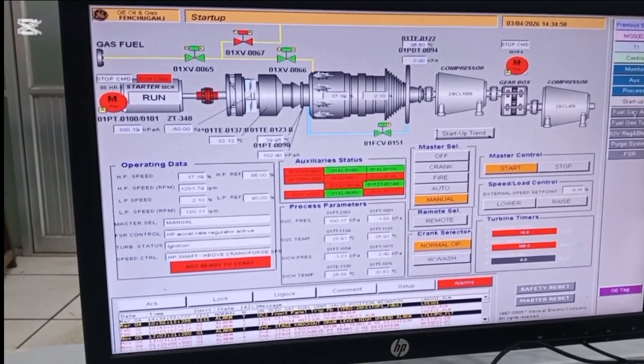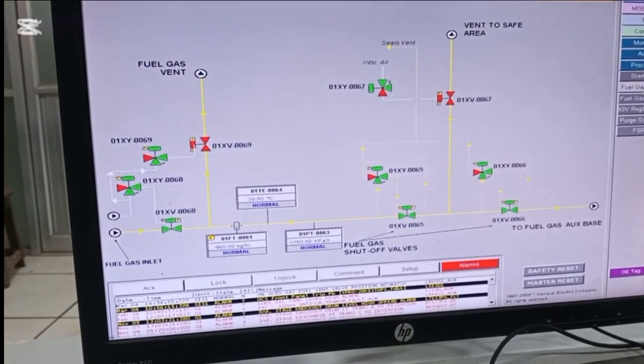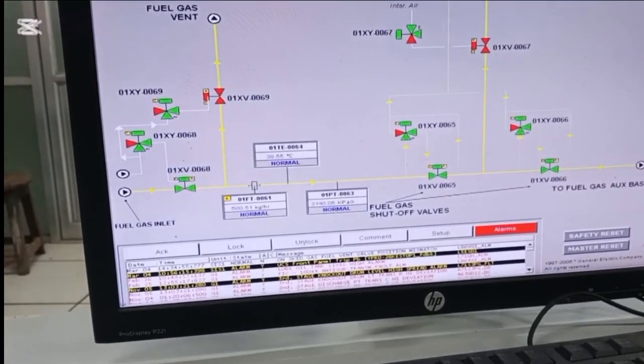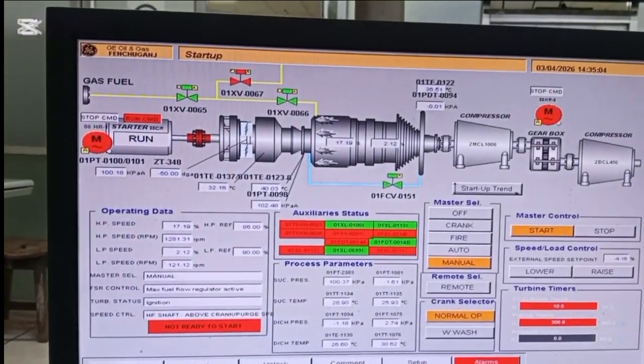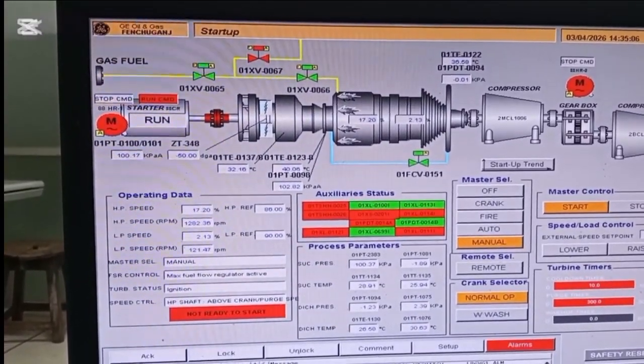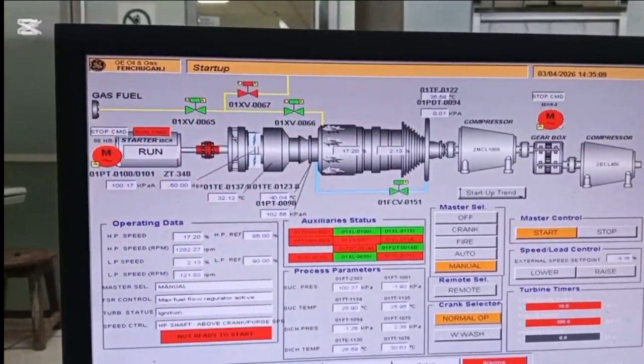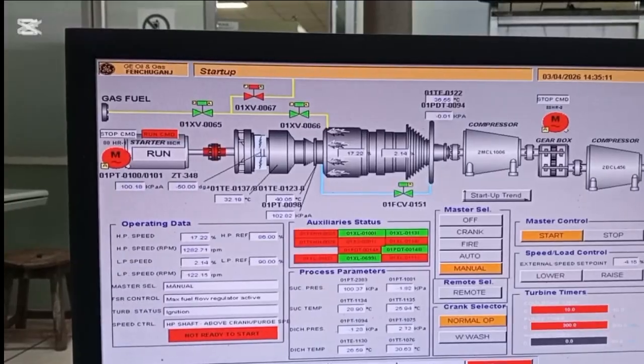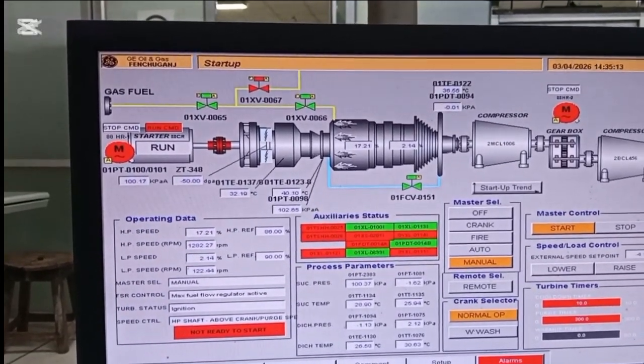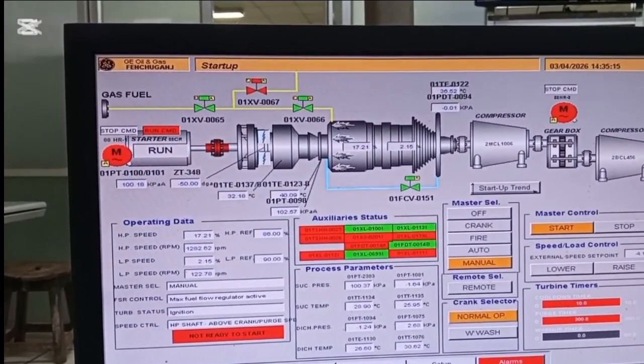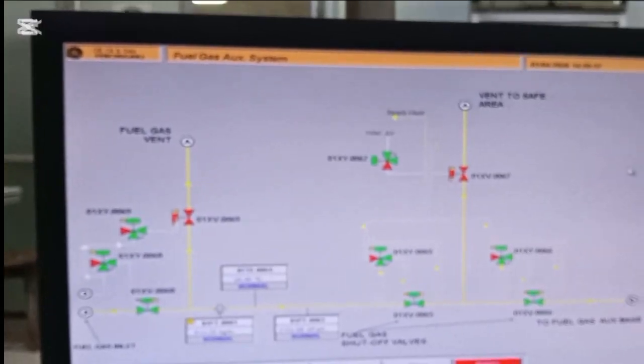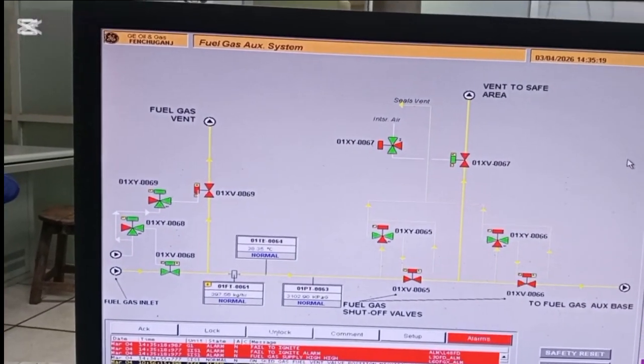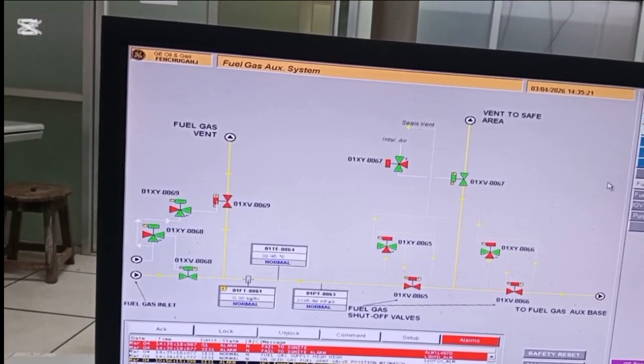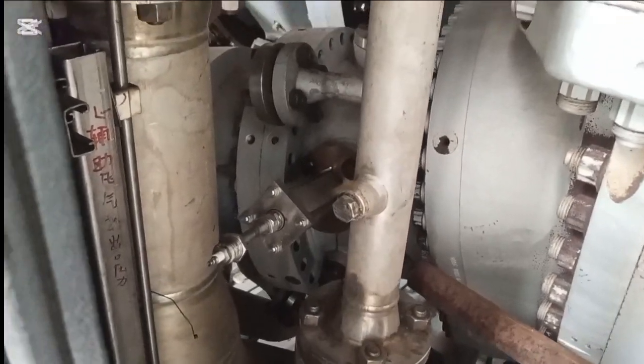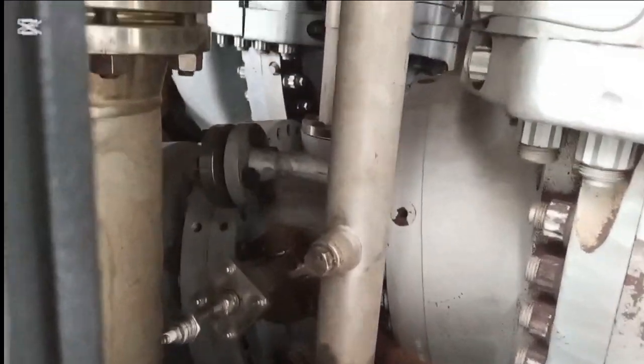Today I will describe and show how to check and change the igniter, that is the spark plug, of a GE manufactured gas turbine. Here the gas turbine is started after the logic sequence has passed, and its starting step is forwarded. After purging completion, the vent valve closed, the block valve opened, and the gas flow is okay. But after that, ignition is not okay.